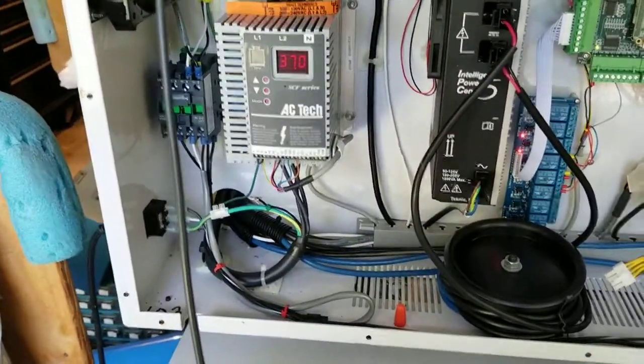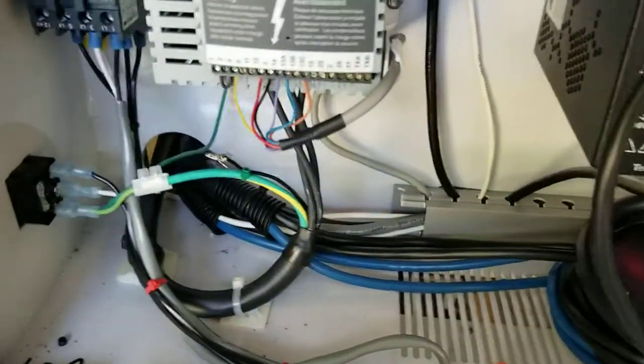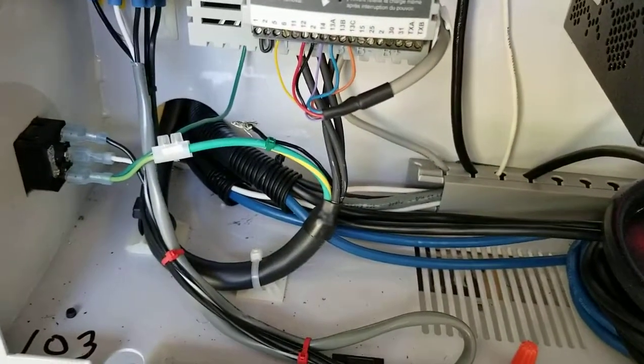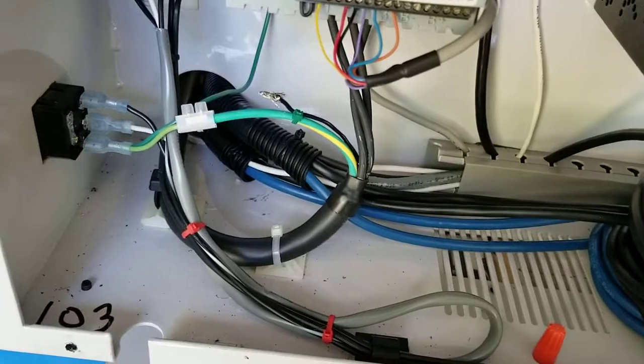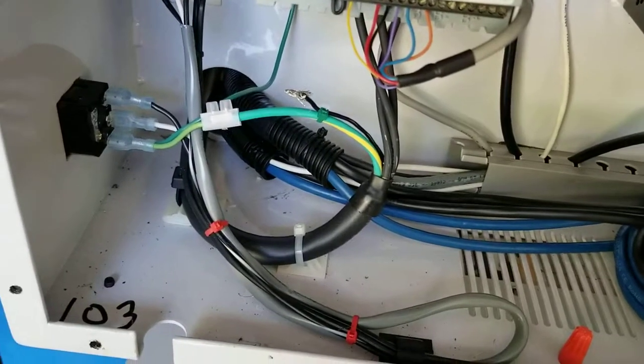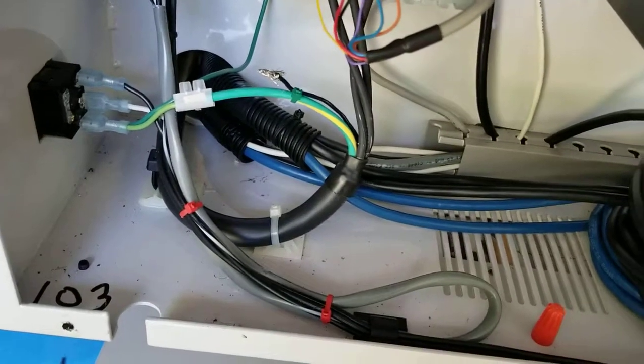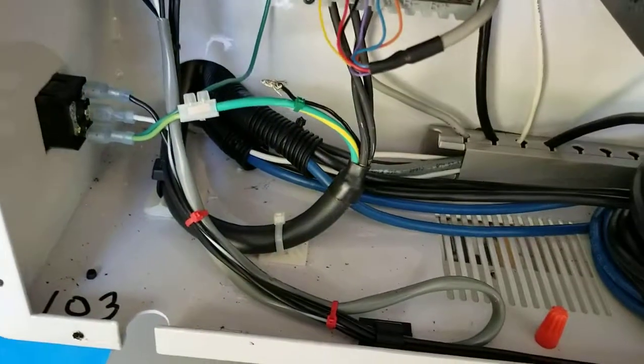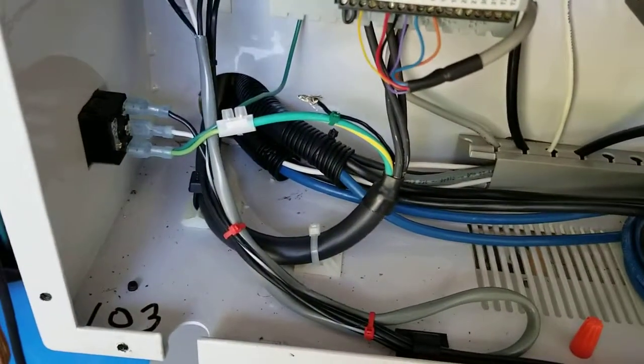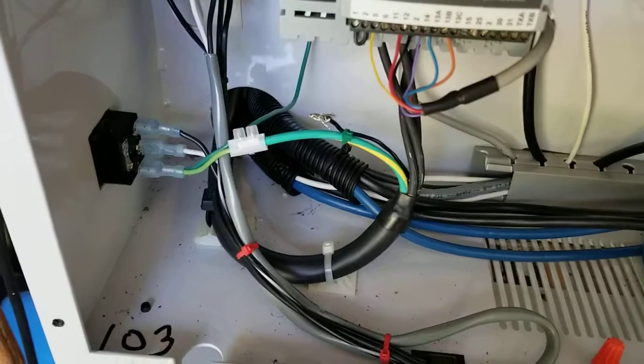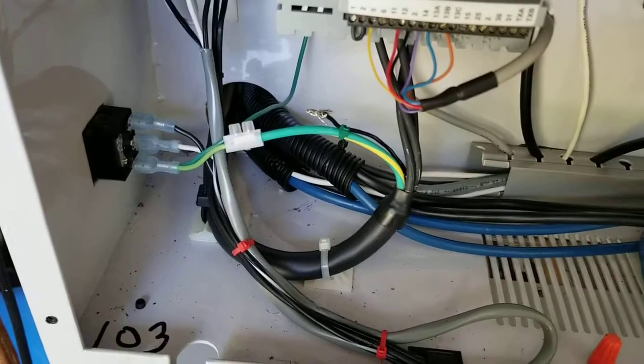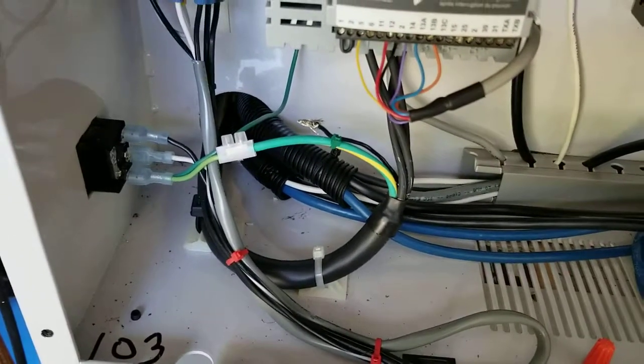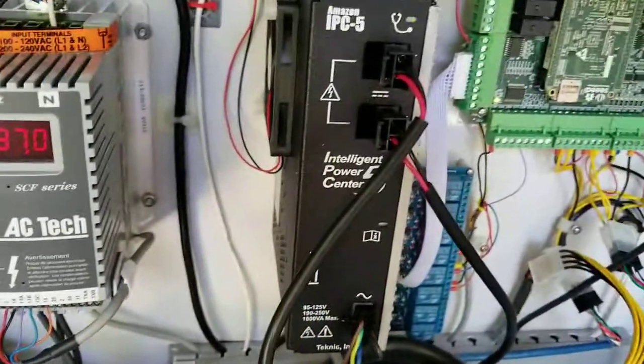Really, the shield is picking up the radiated emissions and kind of converting it. So it's really shutting down a lot of the EMI radiating from the cable. And as long as you take care not to make the VFD cable run alongside parallel with the signal cables for too long a distance, you're pretty much okay. I've had no problems so far with this run.